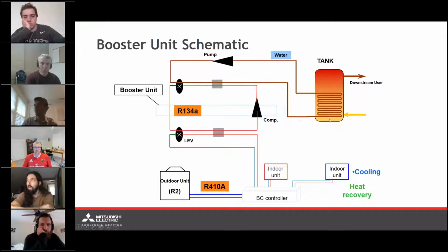So in this particular configuration, the water loop running through this tank is a closed loop. So this isn't going to be introducing any hot water to the tank itself. It's just going to be running through and heating the water within the tank. And this application we could use to ultimately reduce the peak load on the domestic hot water heating system. So if there's an existing fossil fuel driven domestic hot water system, this particular schematic and sequence we can use to ultimately reduce the peak load and pull down the carbon footprint of that particular building.